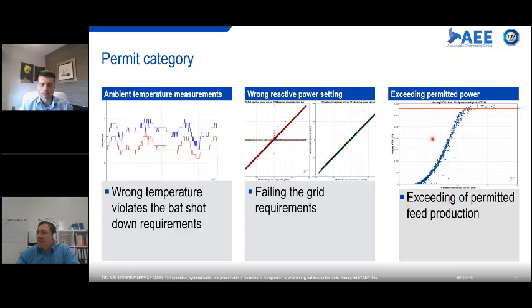And the third, actually the first case for permitting, is where we have a limit. This red line represents the limit of maximum feed-in capacity from your turbine. As you can see, this turbine was exceeding this limit. In this specific case, two rules were actually exceeded. One was the operating permit, which only allowed 3.3 megawatt output, and the other was the requirement by the grid operator.